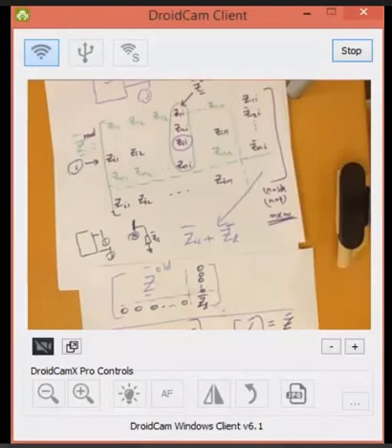The new row is where it is connected to. This bus is connected to bus I, so just repeat row I. If connected to the ground, just replace it with 0. Whatever you have in the row, repeat it in the column. Only one element is left, element n plus 1 by n plus 1, which is ZL plus ZII if connected to I, or ZL plus 0 if connected to the ground.